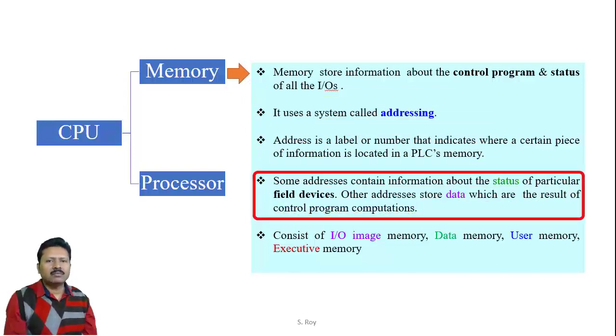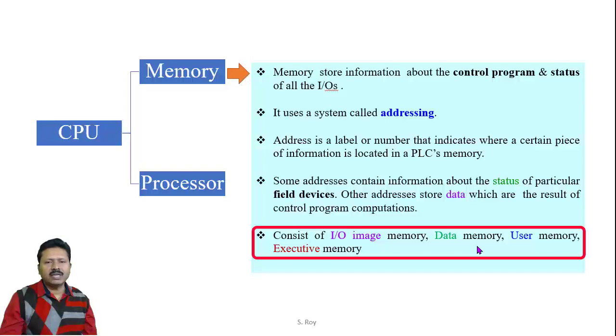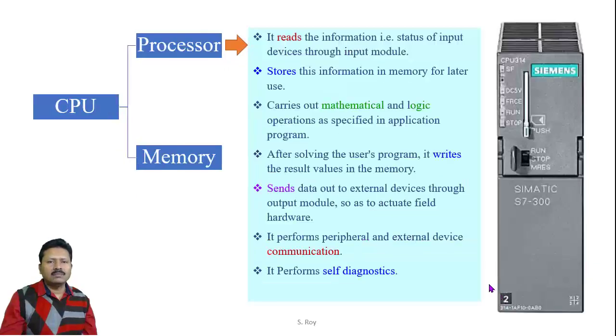Some address contents contain information about the status of a particular field device, and other addresses hold data that is the result of different control program computations. According to function, memory may be classified as input/output image memory, data memory, user memory, and executive memory. Input/output image memory holds the status of input and output devices. Data memory holds the results of different arithmetic computations. User memory holds user-defined programs, and executive memory is mainly for the operating system of the PLC.